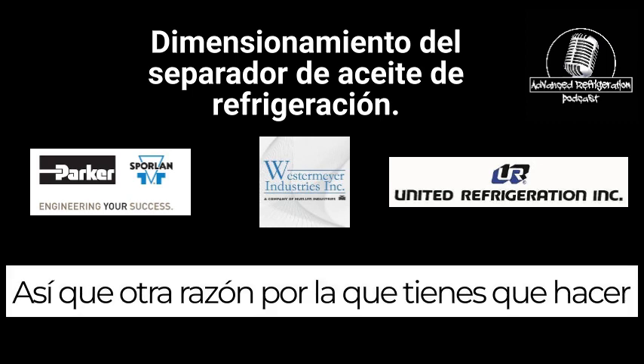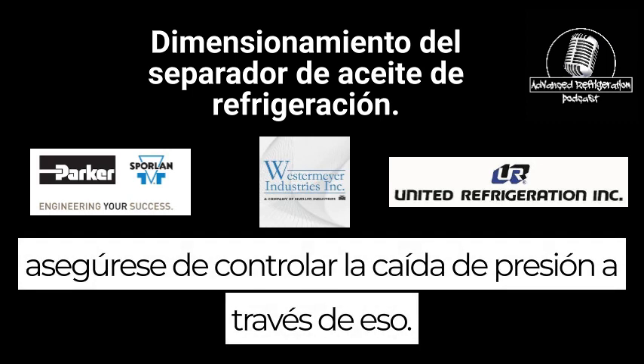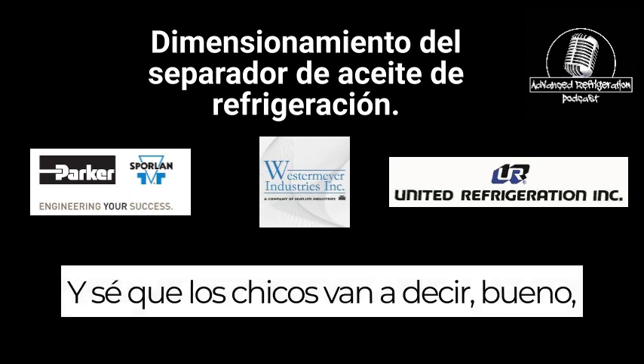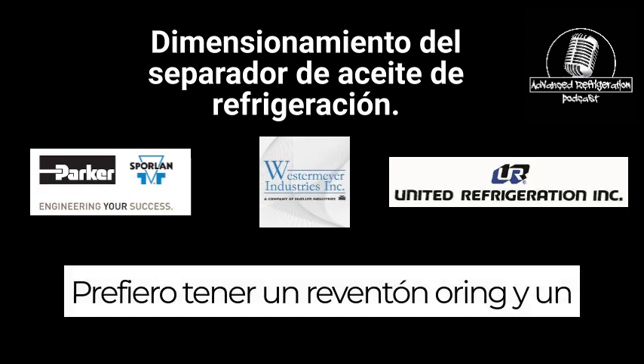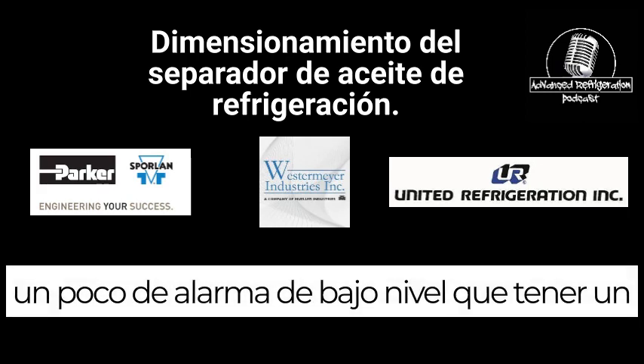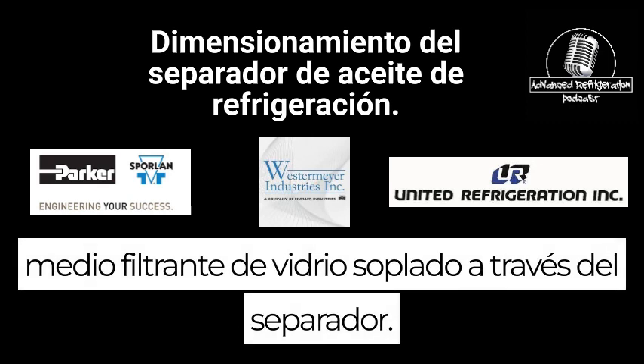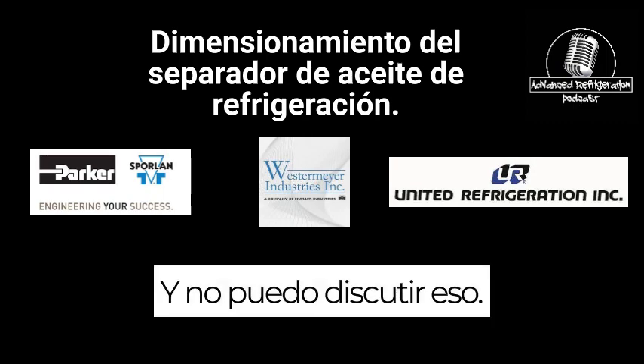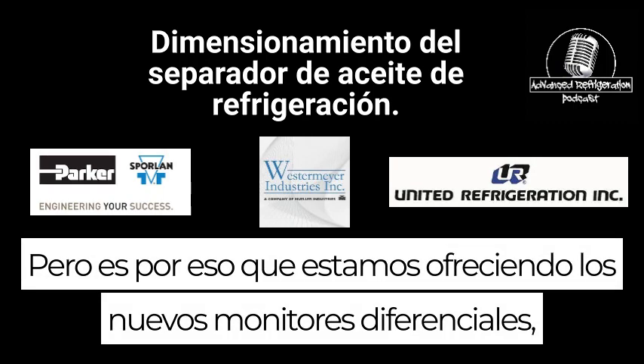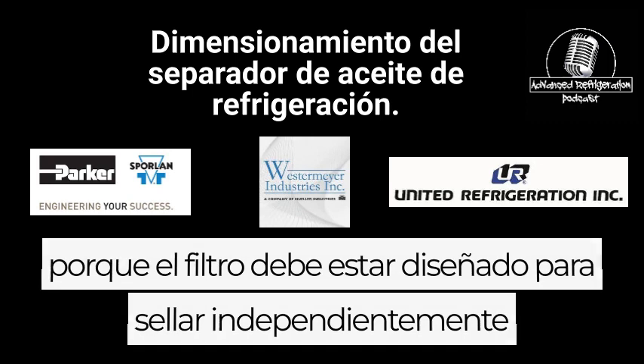So that's another reason why you've got to make sure you monitor the pressure drop across that. And I know guys are going to say, well, I'd much rather have an O-ring blowout and a little bit of an oil low level alarm than have a glass filter media blown out through the separator. I can't dispute that, but that's why we're offering the new differential monitors, because the filter should be designed to seal regardless.